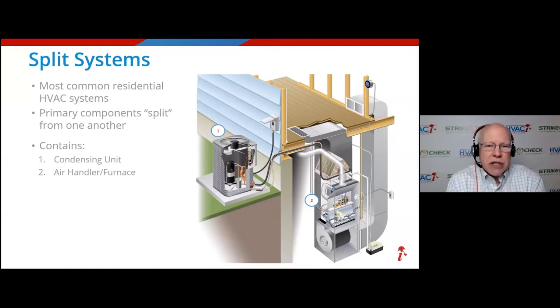But not every unit generates heat. Sometimes it's just the air conditioning equipment. At that point, we would call it just an air handler. Where it gets confusing is, like in our diagram, we have a furnace and we've added an evaporator coil on top of it. So in the summer, we can also share that ductwork and do air conditioning as well. That's where I think it gets a little confusing. But a furnace and an air handler, in the true sense of the statements, are really two very different things. We're going to focus on air handling and cooling today.